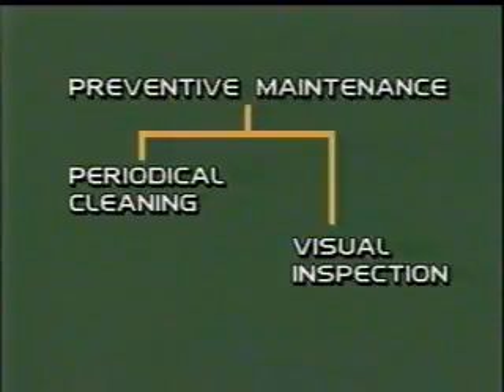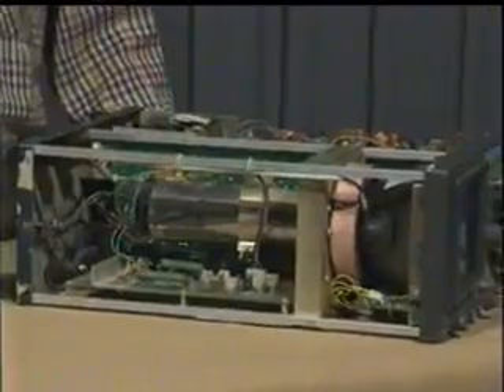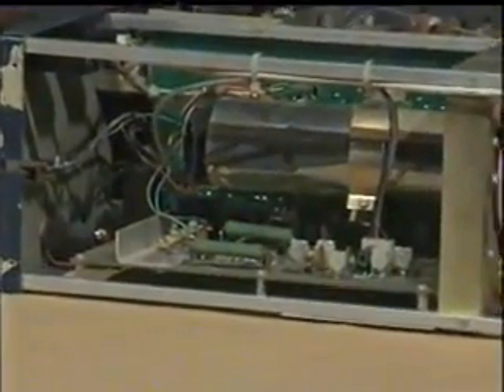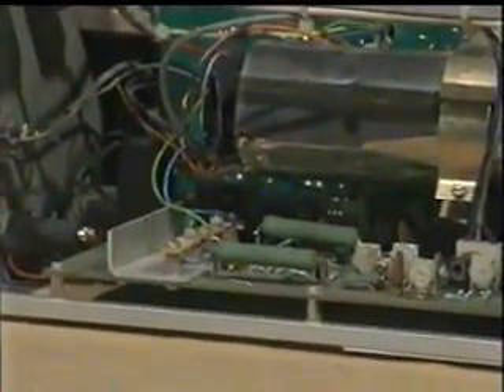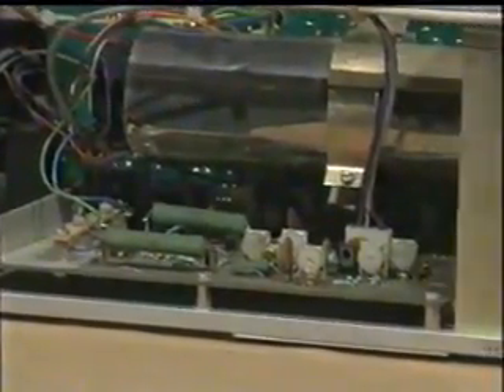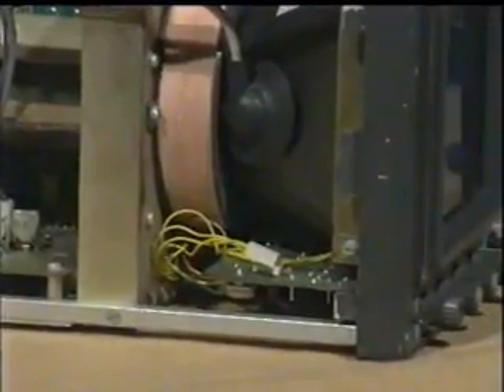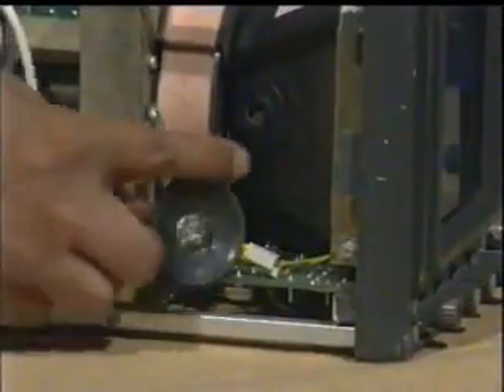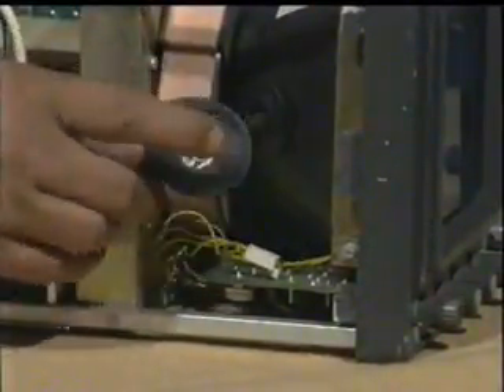Under this category, the equipment is regularly checked for any possible loose contact, dry solder. The internal cleaning of the oscilloscope should be done regularly to avoid the accumulation of dust. Special attention should be paid to the high voltage section and the connectors. Any conductive particle in this region may result in arcing.